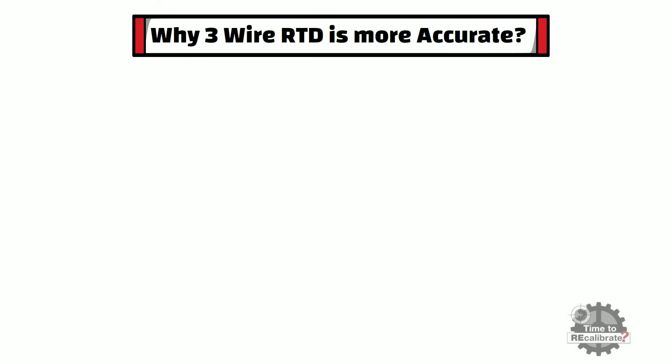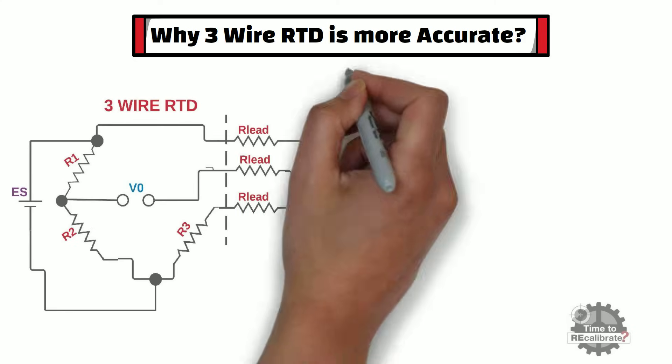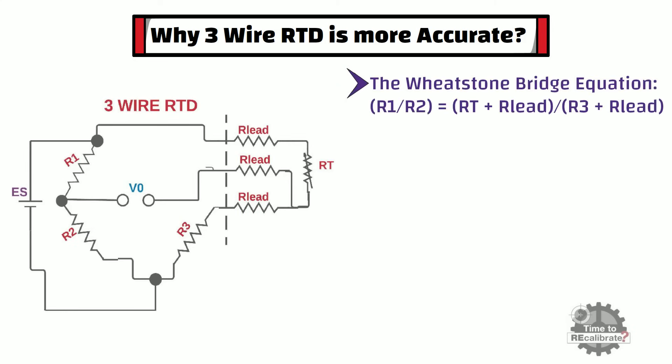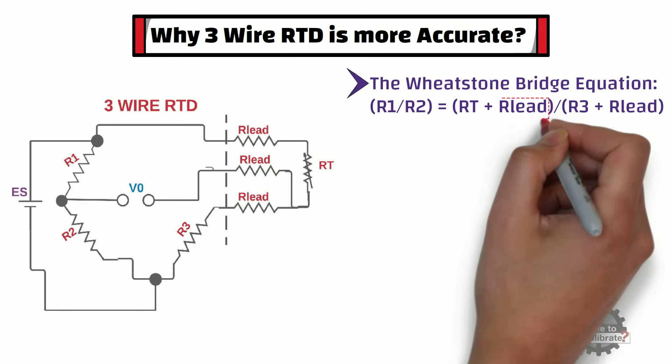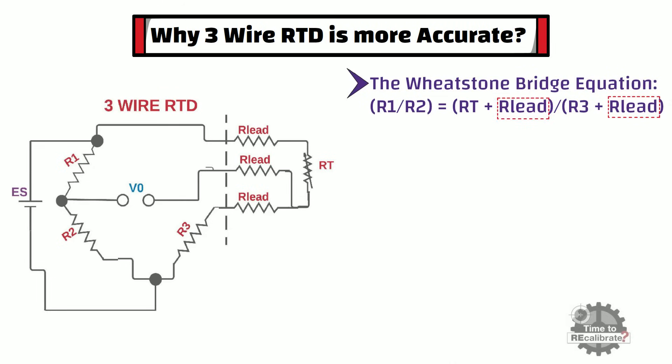Now let's understand in detail why 3-wire RTD is more accurate than 2-wire RTD. As you can see, this is the Wheatstone Bridge equation for 3-wire RTD. In this equation, both the numerator and denominator have the lead resistance, and because of this, the right-hand side ratio does not get affected due to lead resistance. In other words, both lead resistors eliminate each other's effects in the circuit.